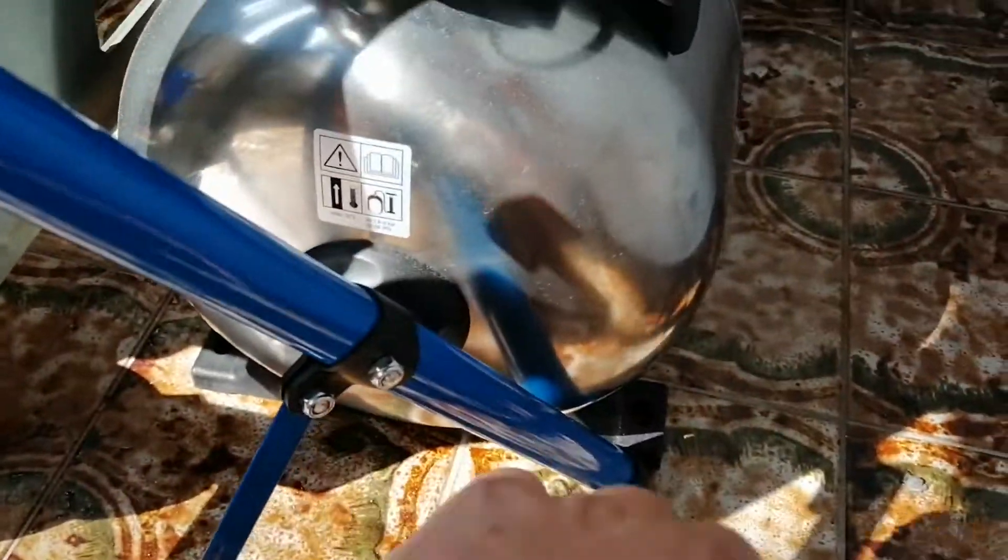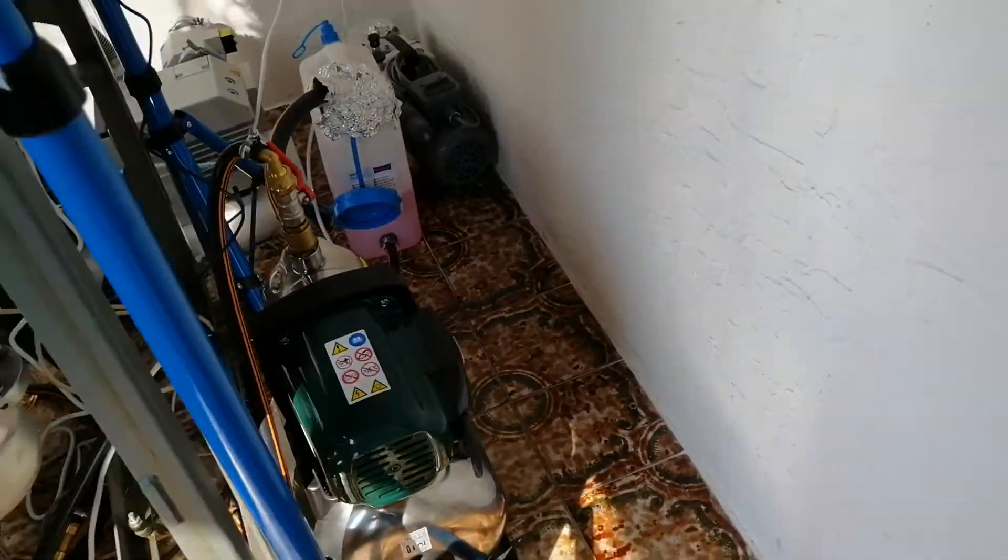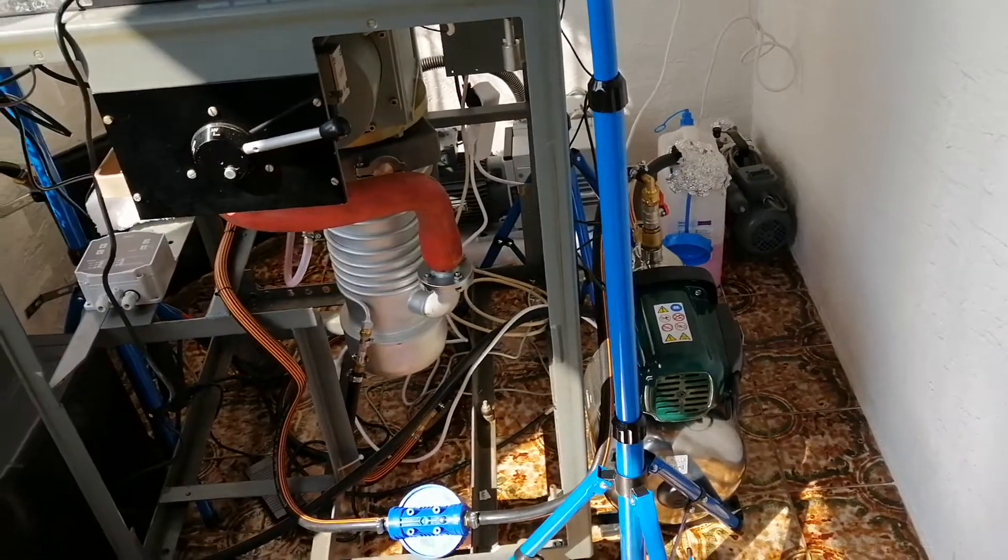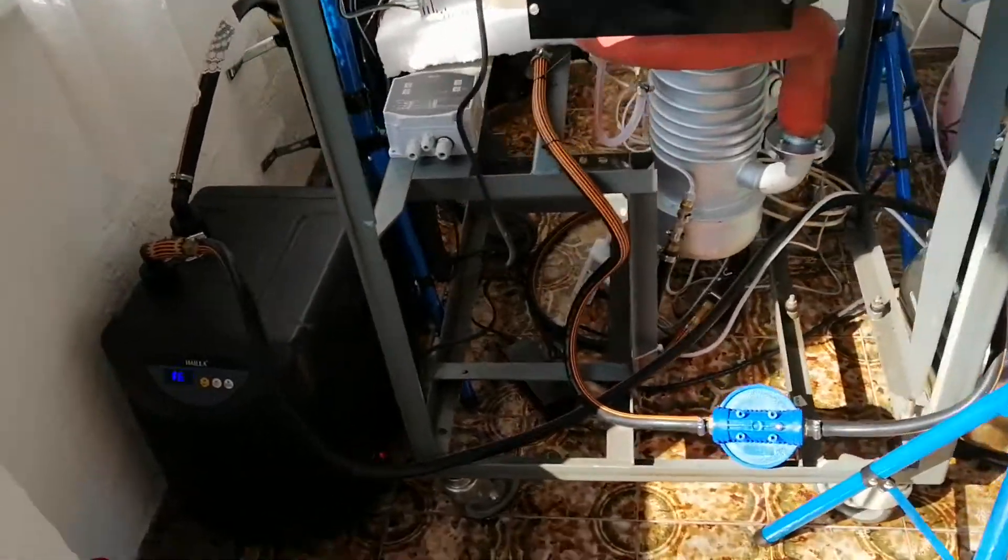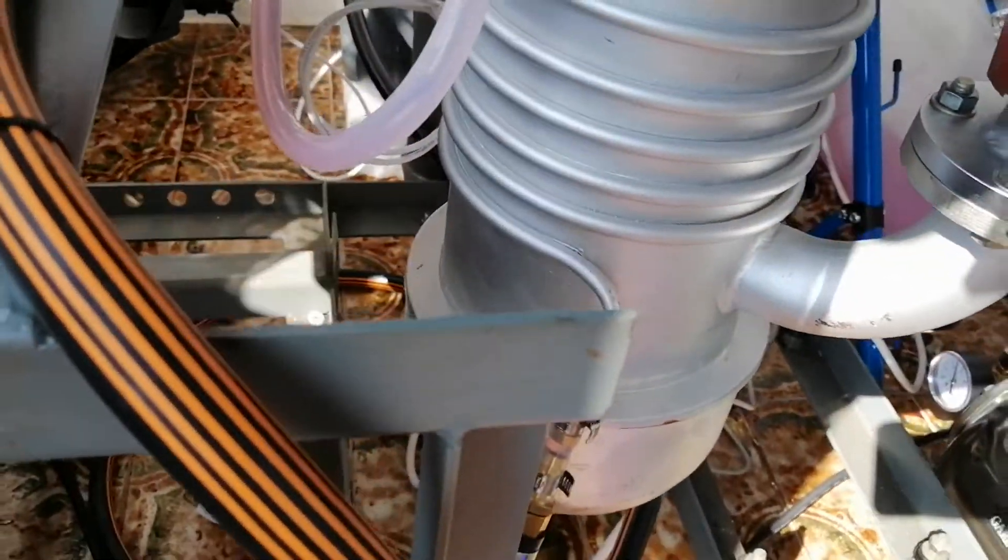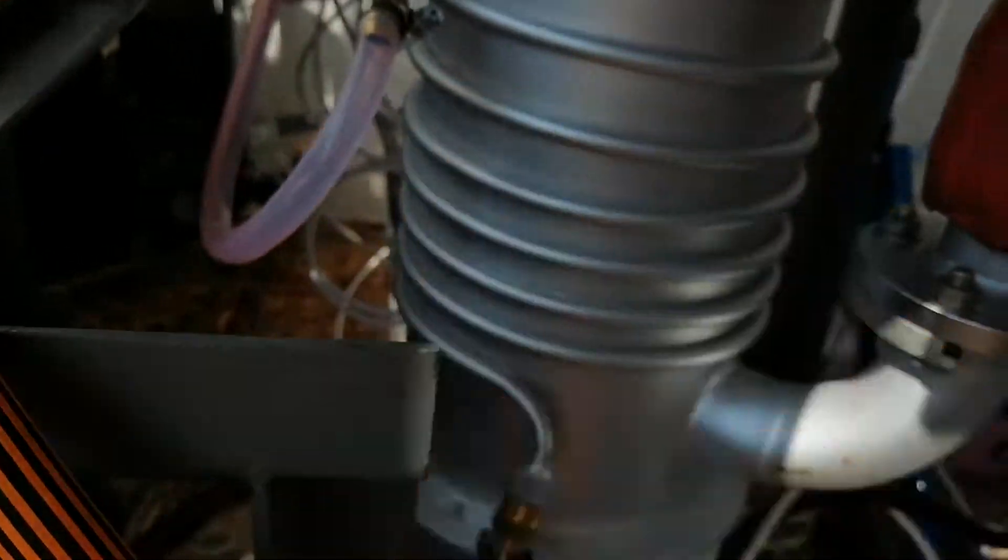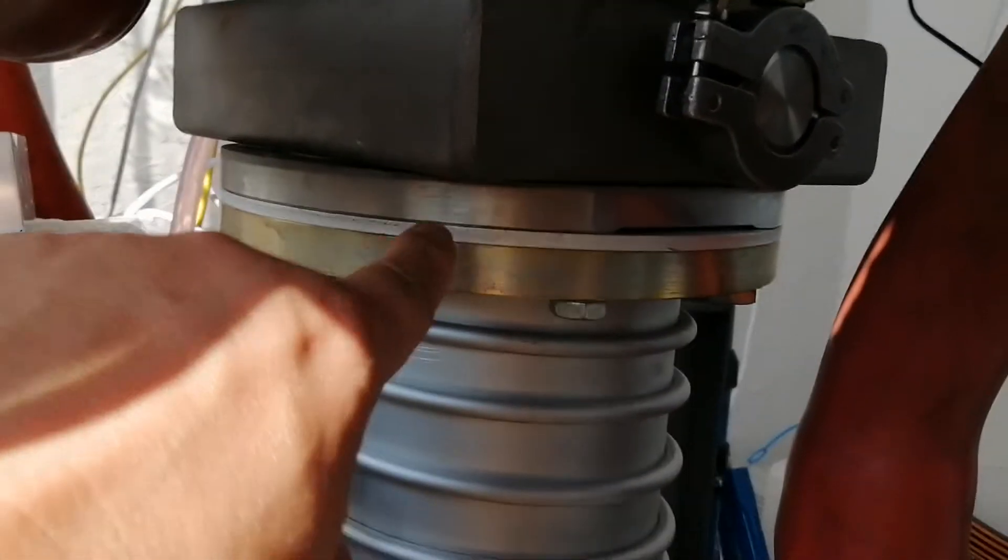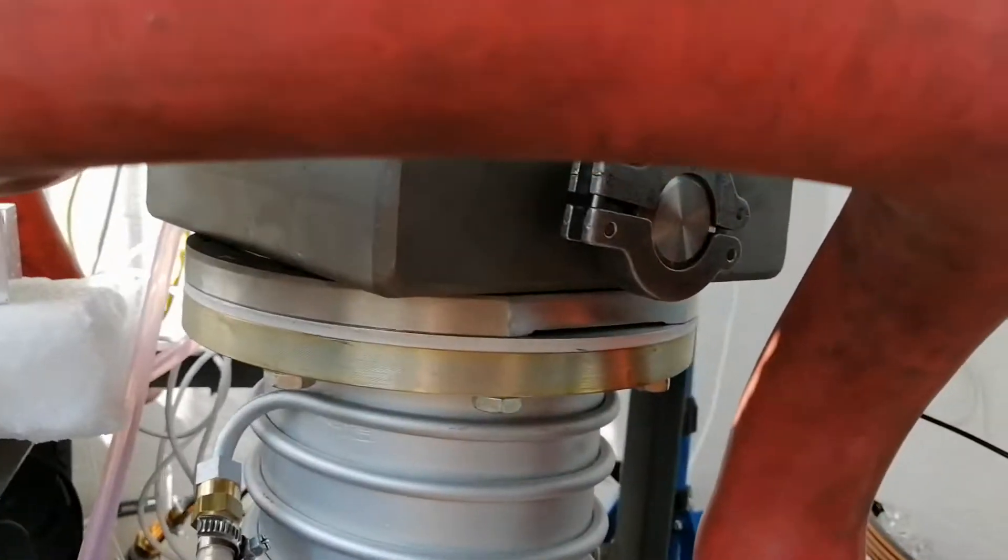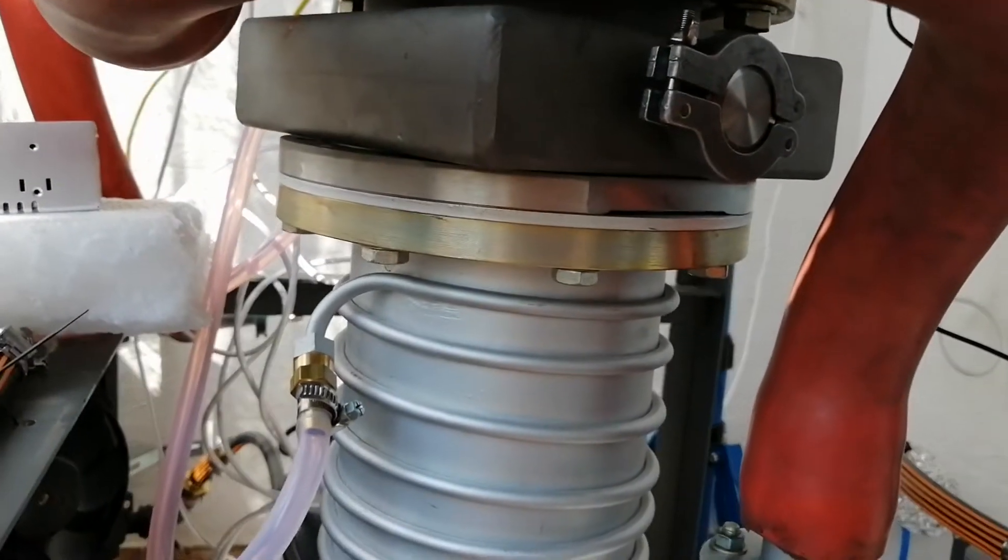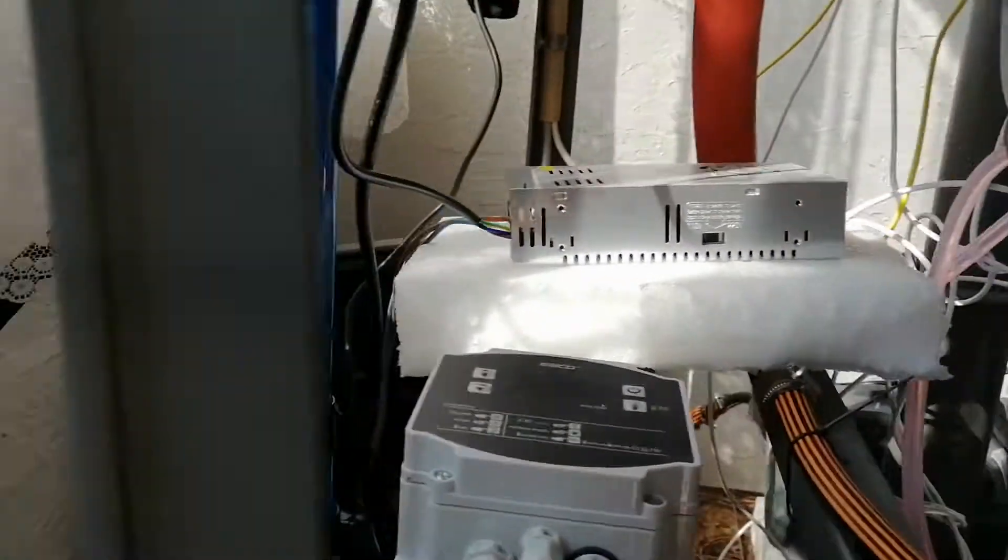Here is pressurized, so it's keeping the pressure. Then if the pressure is too low, it sucks water in again and then it can put it here into this cooling spiral and into the baffle. The baffle needs to be cooled because some oil could get into the chamber, so we want to cool it down.